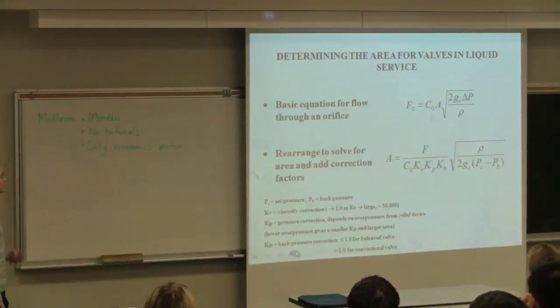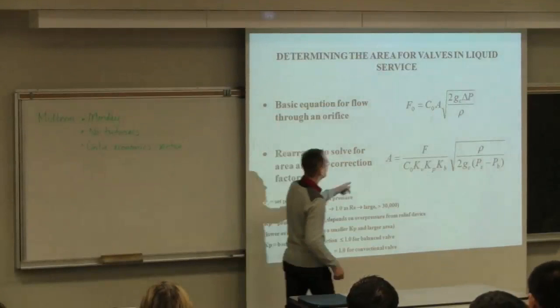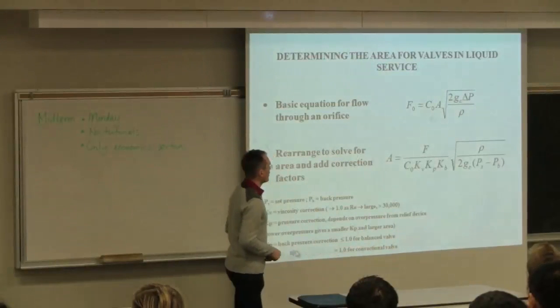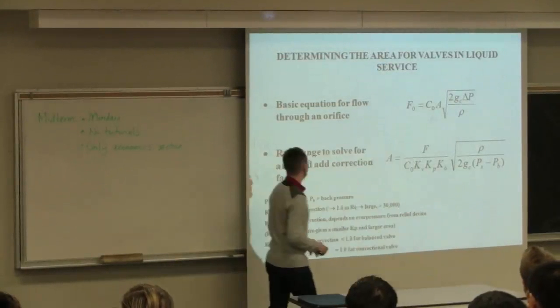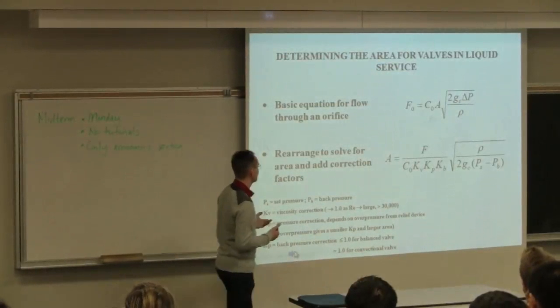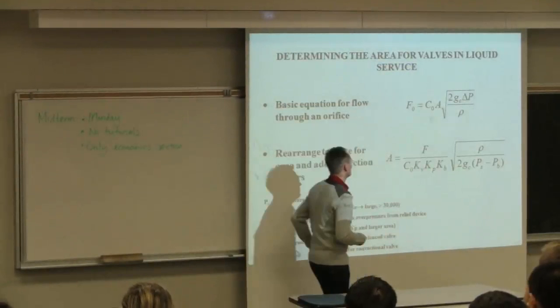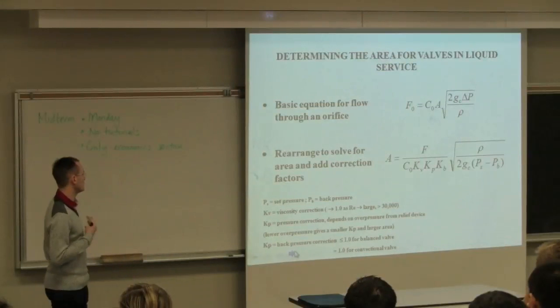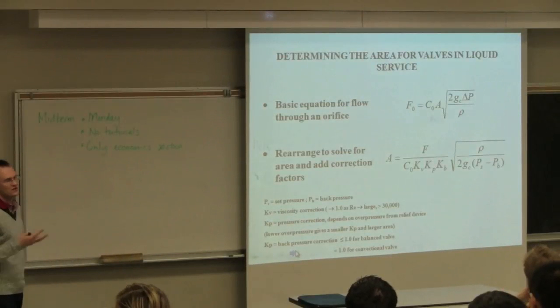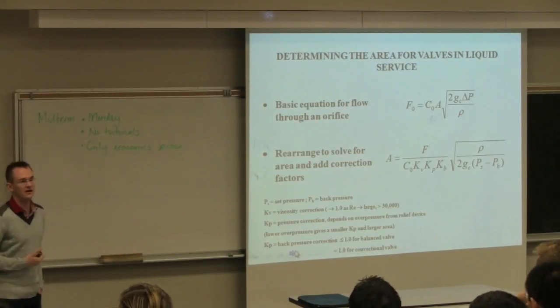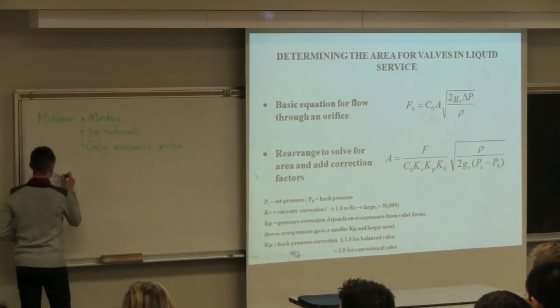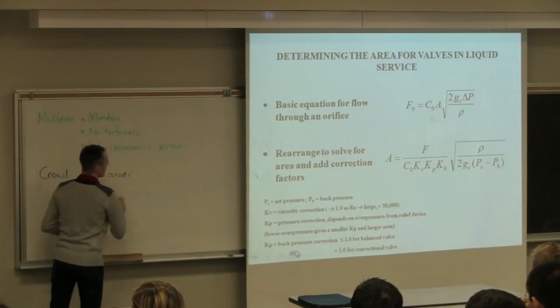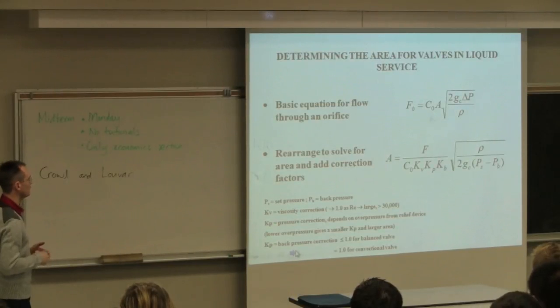So how do we size those relief valves once we know the flow we anticipate? This is our maximum flow. We use the standard equations for flow through an orifice that you would have seen in your fluid flow course. We simply rearrange it for the cross-sectional area there. So the purpose of this course isn't for us to go through these and apply these calculations, but to recognize that there is a procedure to do it.